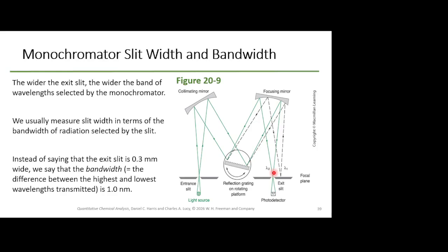Now keep in mind, there's fractions for wavelengths. So it's not like you can get it to exactly one wavelength for basically almost any instrument. Lasers do a better job of that usually anyways, but yeah. But the wider this slit right here, the more range of a wavelength you're going to get. And so you're going to affect your resolution, aren't you?